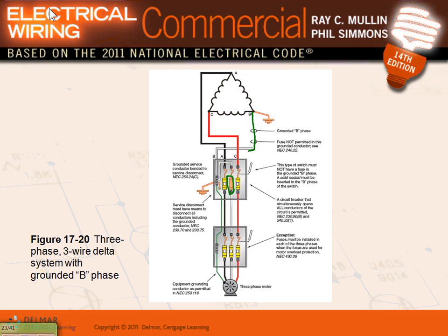So how are they going to land it in here without fusing it? What they do, guys, is they bring it in here and they put a connector. Can you see how they did it? I don't know if you can see. They came over here, landed here, came back here, and they went down into the system. But they can't use a fuse, so they use a copper connector. Looks like a fuse, fits exactly like a fuse would fit, but it's really nothing other than copper. Copper fuse, no, nothing in it. Cover connector. They use it for a delta.